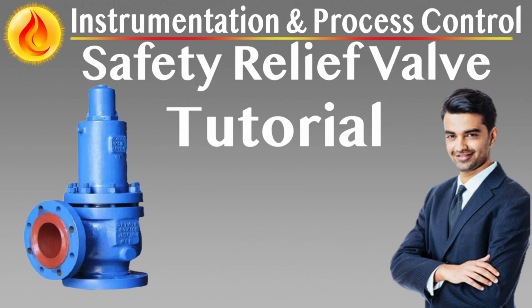When to use balanced relief valves. Required when built-up back pressure exceeds allowable levels for non-balanced valves. Mandatory in systems where back pressure exceeds 10% of set pressure, especially complex header systems with multiple valves. Closed discharge systems with elevated or varying downstream pressure must be selected when stable valve performance is critical and back pressure exceeds 25% of set pressure.